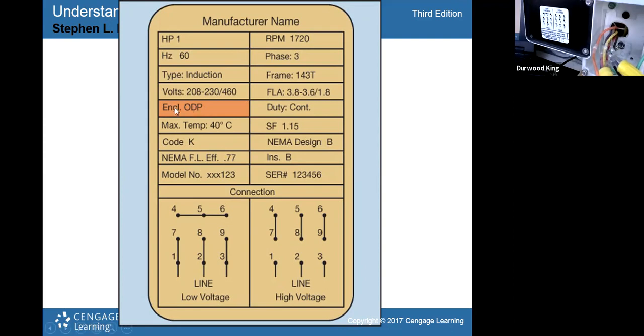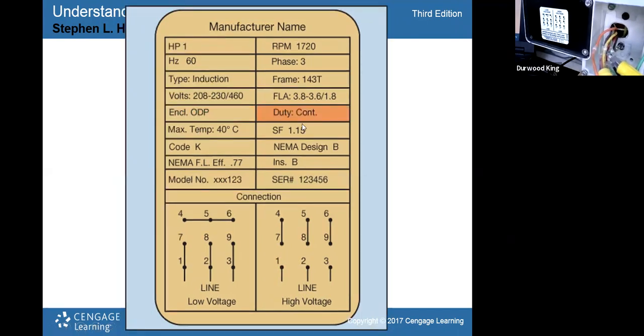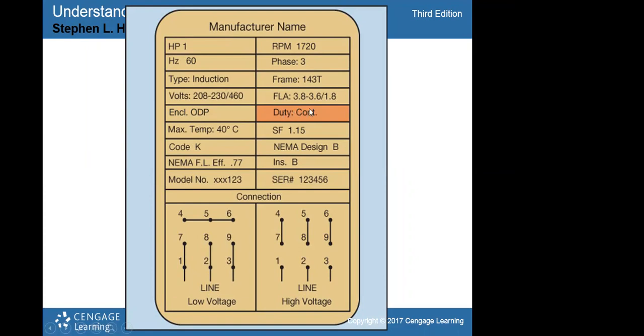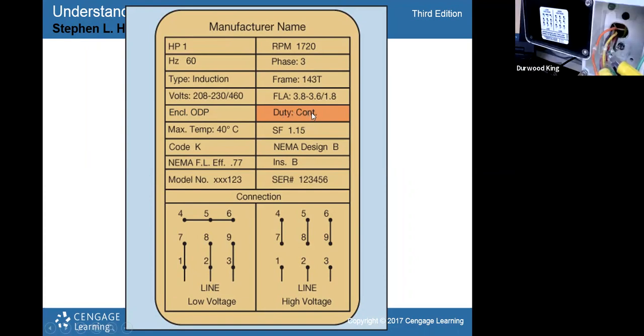So for the enclosure, it could say TEFC, which is totally enclosed, fan cooled. And if it said EXP, it would be explosion proof. Some motors are explosion proof. They can actually be used in flammable areas, or around a feed mill where you've got explosive dust particles, for instance. Then the duty cycle: is it a continuous duty motor, or is it one that's not rated to run all the time, which would be an intermittent duty?